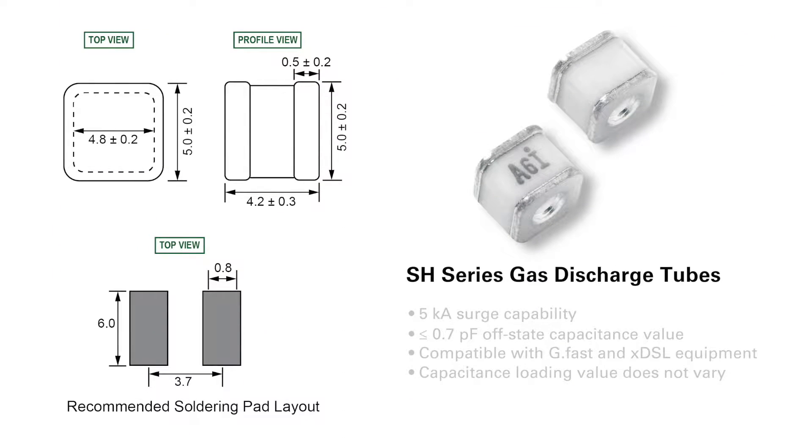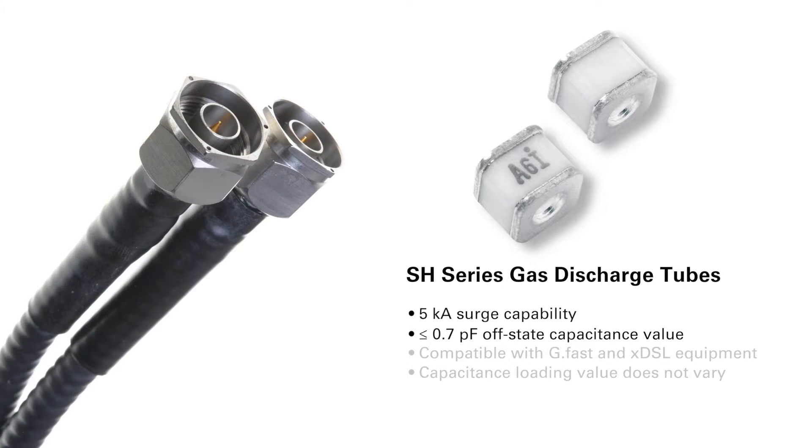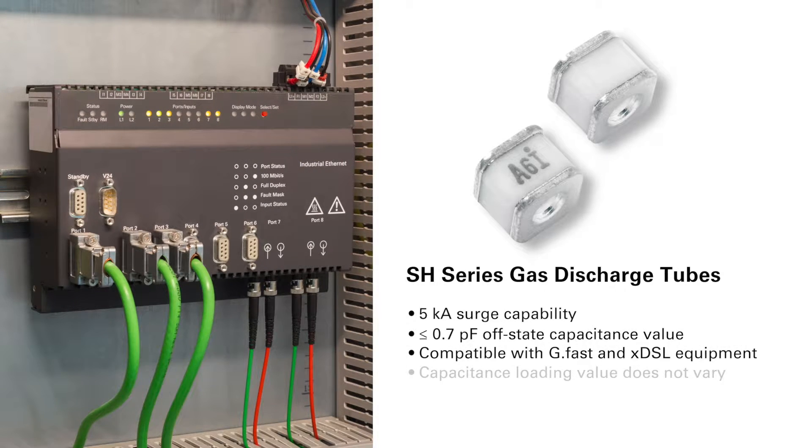The SH-series GDT is the smallest squared gas discharge tube available today with a 5 kiloamp surge handling capability and a less than or equal to 0.7 picofarad off-state capacitance value. Its ultra-low off-state capacitance minimizes insertion loss and any possible signal degradation, so it's compatible with high speed, wide bandwidth applications such as GFAST and XDSL equipment.